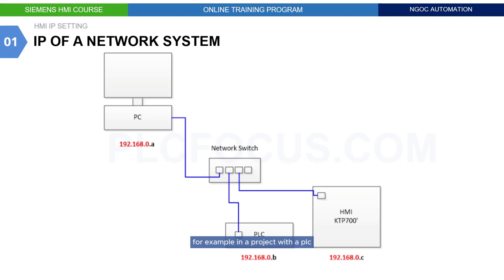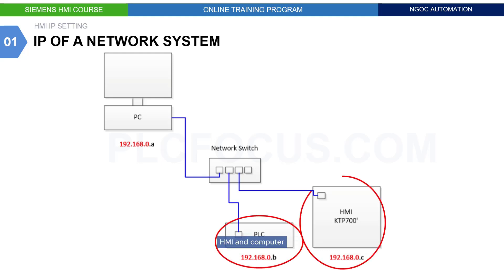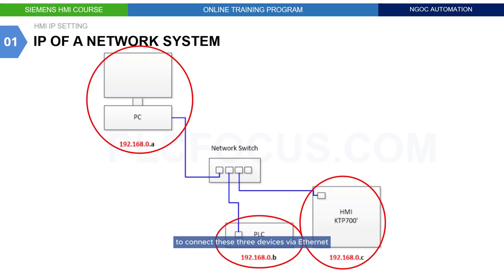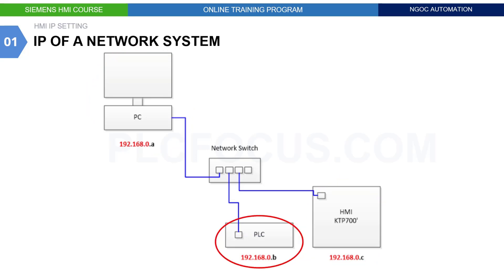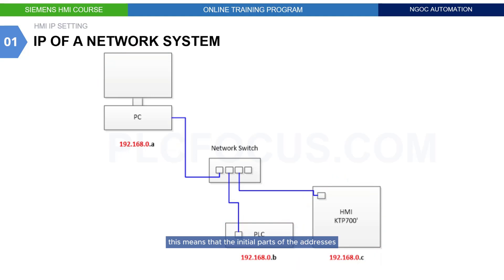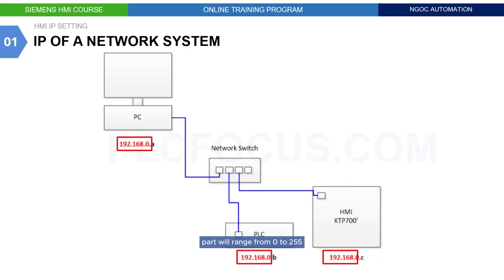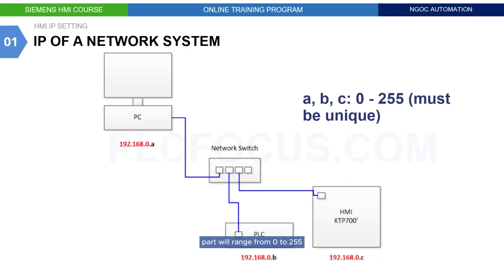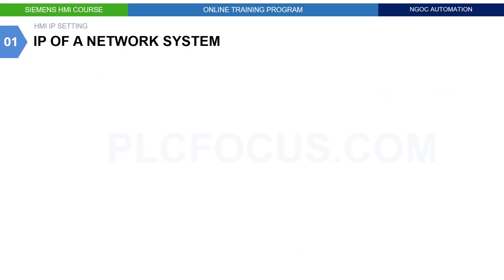For example, in a project with a PLC, HMI, and computer, to connect these three devices via Ethernet, all three must be in the same network layer. This means that the initial parts of the addresses must be the same, and the last address part will range from 0 to 255, but they must not be the same.